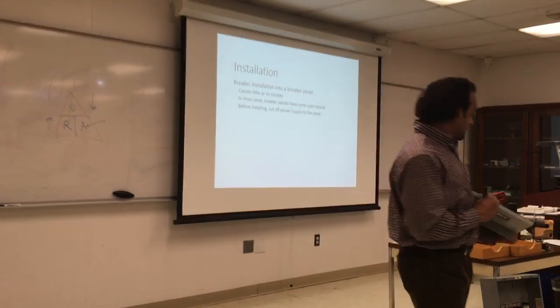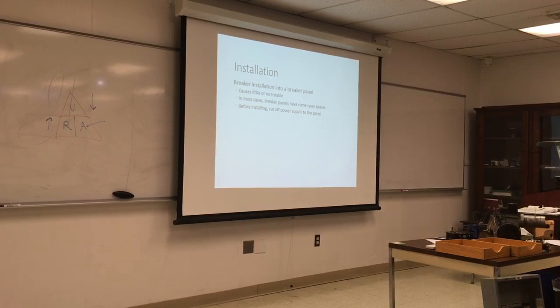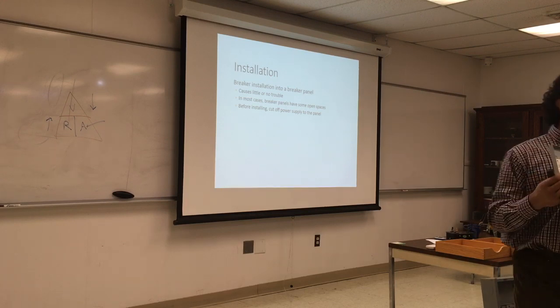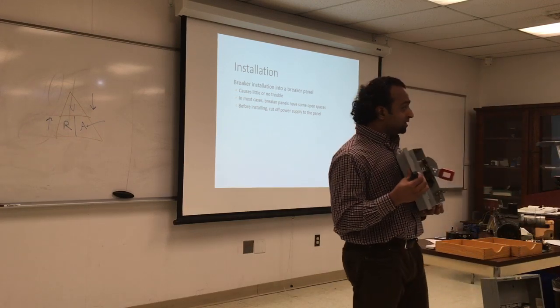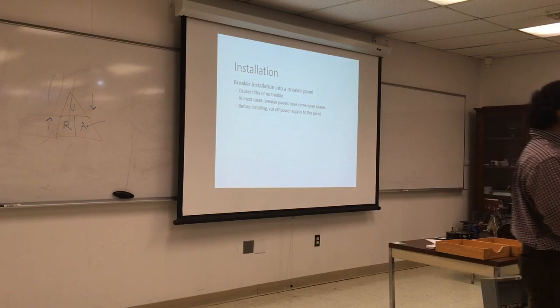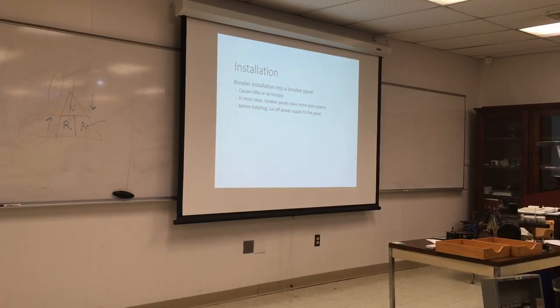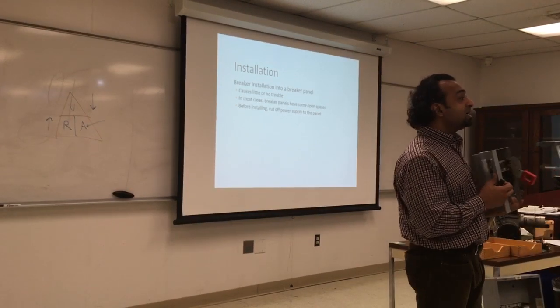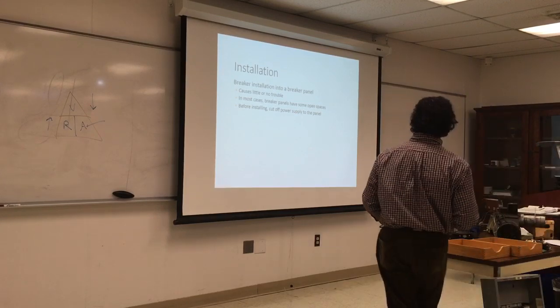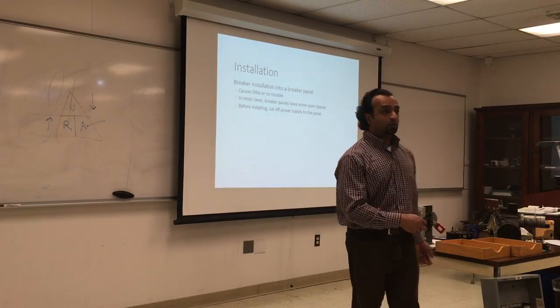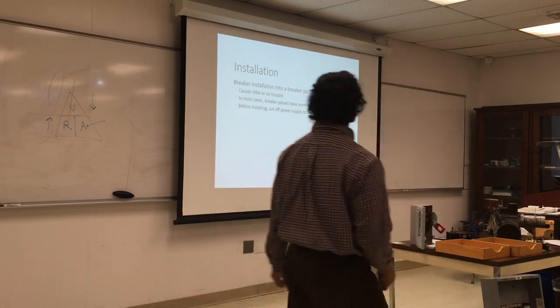Another piece of information. Do we install this? No. A certified electrician should install this. It should be next to your equipment, and you can connect your boiler or your AC to the control panel. Make sure whoever installed it is a certified electrician. Take the name and information, and you can check the gauge of the wire all the way from the disconnect switch to the control panel. Make sure it's the correct information. If you have equipment that exceeds the gauge required, you can request the wires to be changed before you install your equipment.